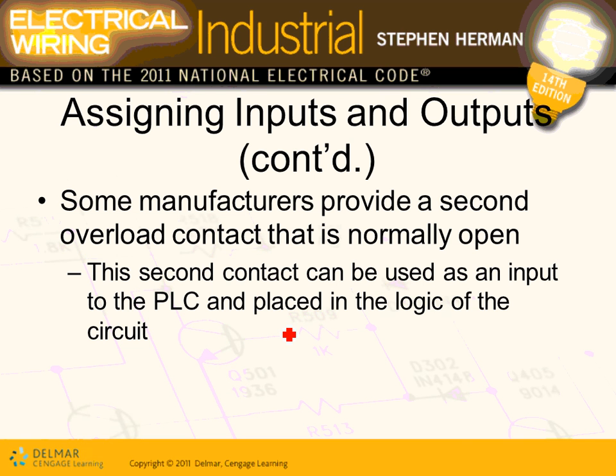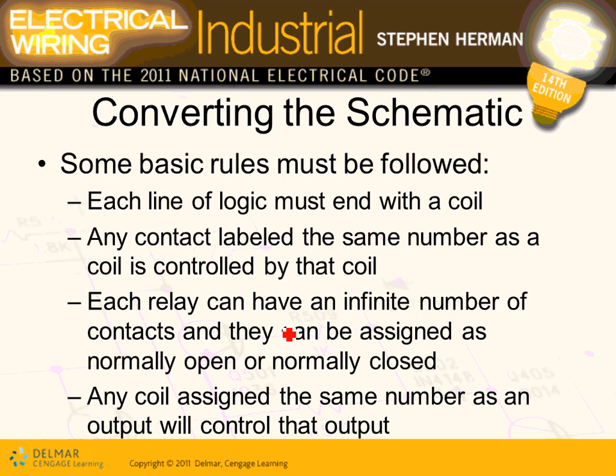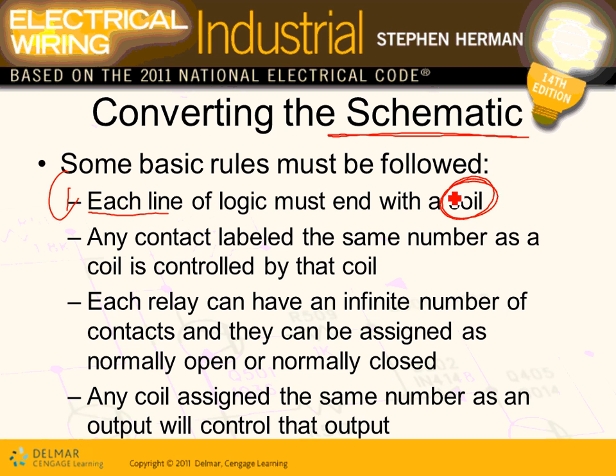When you do the schematics, here's the rule — rule number one: each line must end up with a coil. A coil is a load. If you just take contacts between L1 and L2 with no coil, you know what you're going to have? A short circuit. You have to end up with a coil.